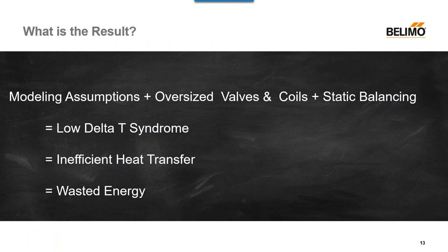What is the result of these actions? Modeling assumptions lead to oversized valves and coils. We have static balancing. All of these together result in low Delta T syndrome — overflowing coils and inefficient heat transfer. We're not utilizing the heat transfer because we're passing water through those coils too quickly. In essence, we're wasting energy and contributing to a larger carbon footprint.